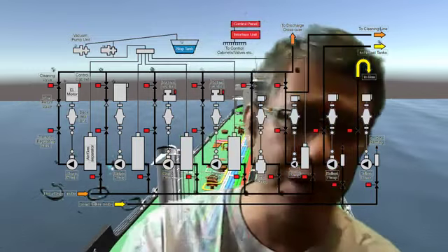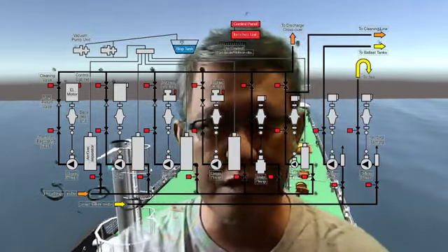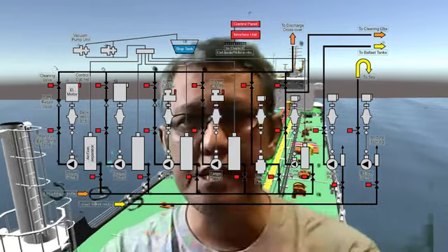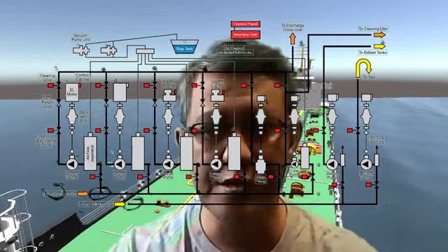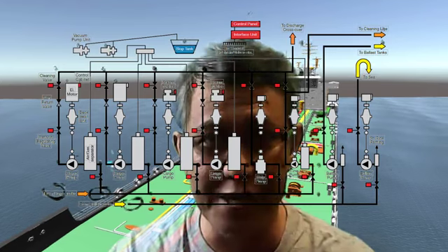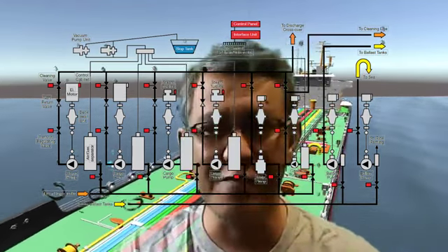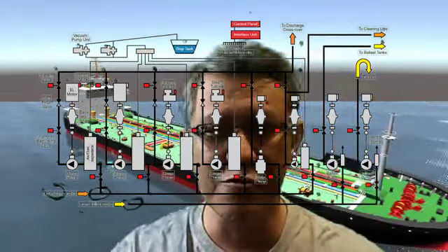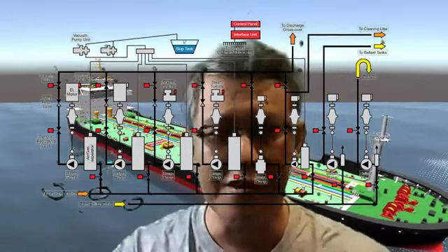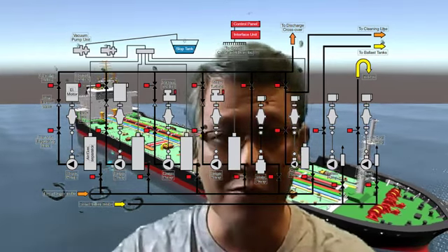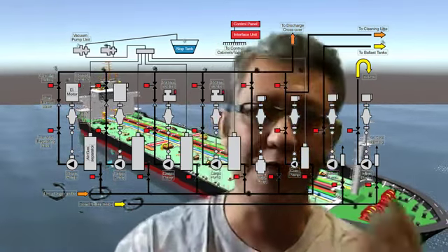And so the AUS will come into the picture, as you can see here in the diagram. When the tank is full, the centrifugal pumps are quite active because of the weight and the gravity of the cargo. But when it gets down to its level, of course it loses suction, and the net positive suction head available is becoming lower and lower, as I mentioned earlier.